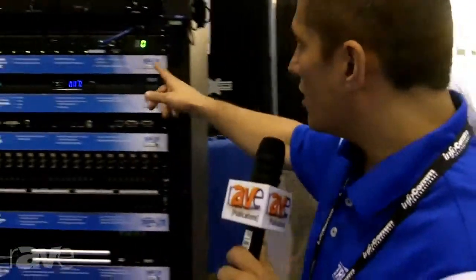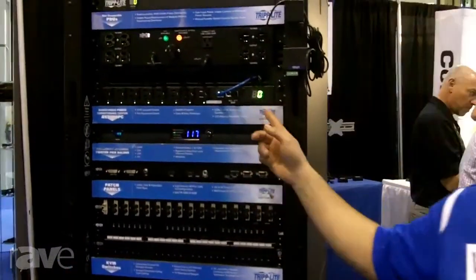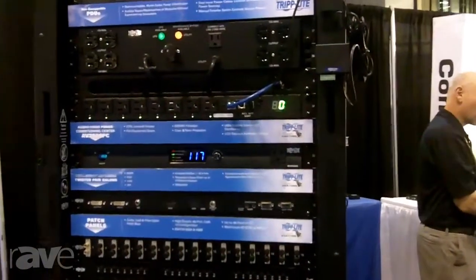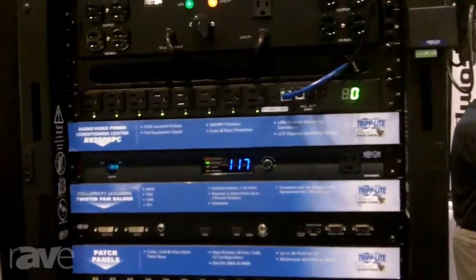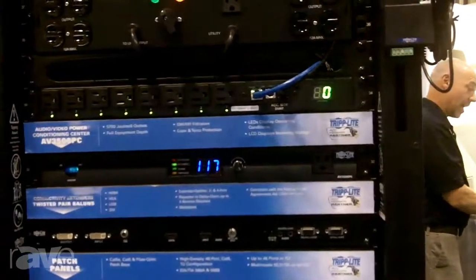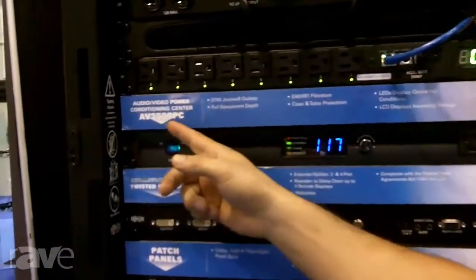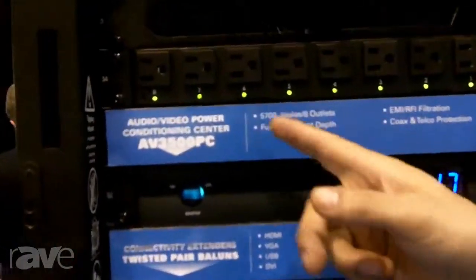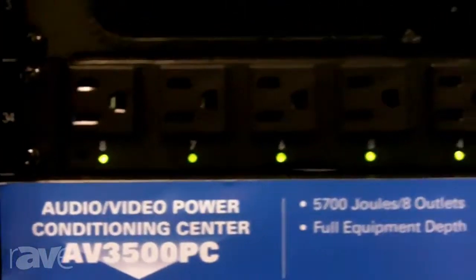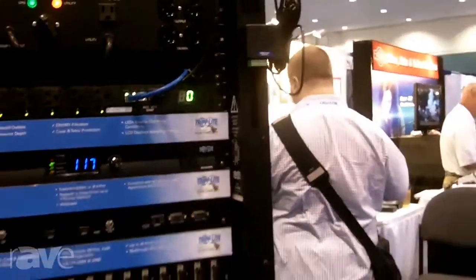We have a couple of different rack systems here, a horizontal and a 1U form factor. You're going to get total power control, so you can do outlet sequencing. For instance, outlet number 1 turns on instantly, put maybe a 5 or 10 second delay on outlet number 2, so on and so forth. So you power sequence equipment one after another, everything's not coming on at the same time.